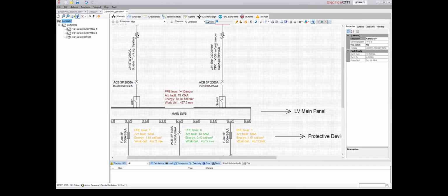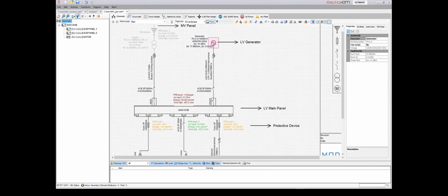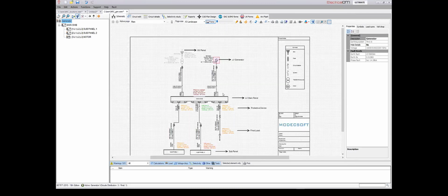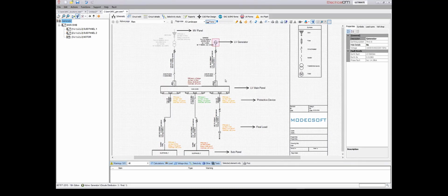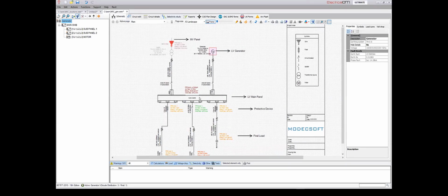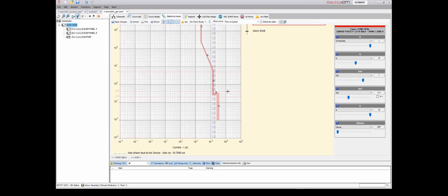Okay, so what this is telling us is that it's very important to consider the cases where the short circuit will change in the system. So if we have another source that can operate in the system, it's good to make sure that we investigate and evaluate all the cases here to make sure that we address the worst case for the PPE category. Okay, so in this case, we need to make sure that we make the necessary adjustments for the equipment, turning on the arc flash option here.